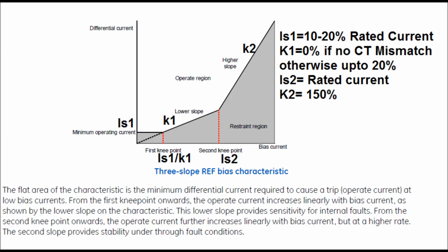From the first knee point onwards, actually there are two knee points. From the first knee point onwards, the operate current increases linearly with bias current, as shown by the lower slope, that is K1 in the characteristics. This lower slope provides sensitivity for internal fault conditions. Normally K1 is set at 0 to 20% depending on the CT ratio error. If there is no ratio error present in the CT, then K1 can be set as 0%. If CT mismatch or CT ratio error is present, then it can be set up to 20%.